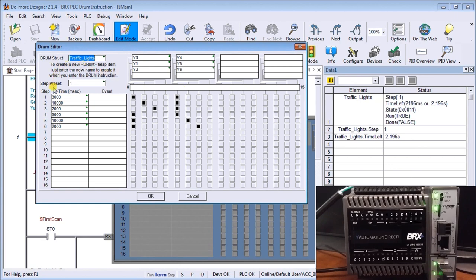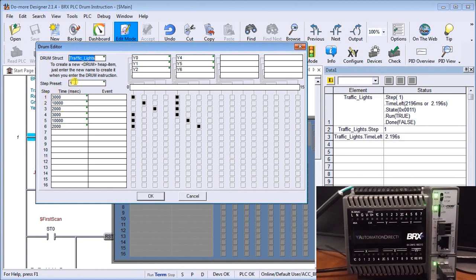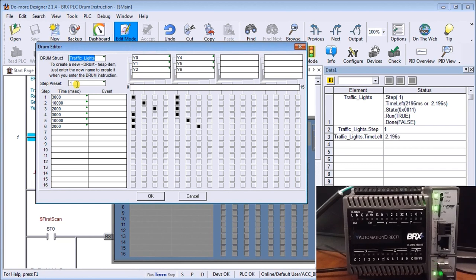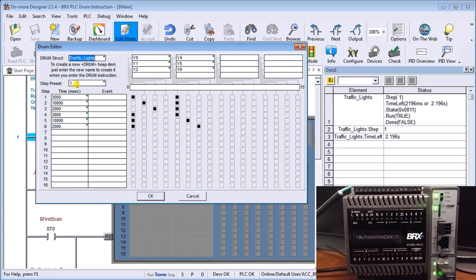So we call this one traffic lights. Our step preset is set for one. This means that when we have a reset to the drum instruction, it will go back to step number one. If we put a variable in here like a register like V0, then we can set these to different numbers and when we hit the reset it will go to that particular place. And we've done this before in our example of the palletizer that we did with the factory IO.